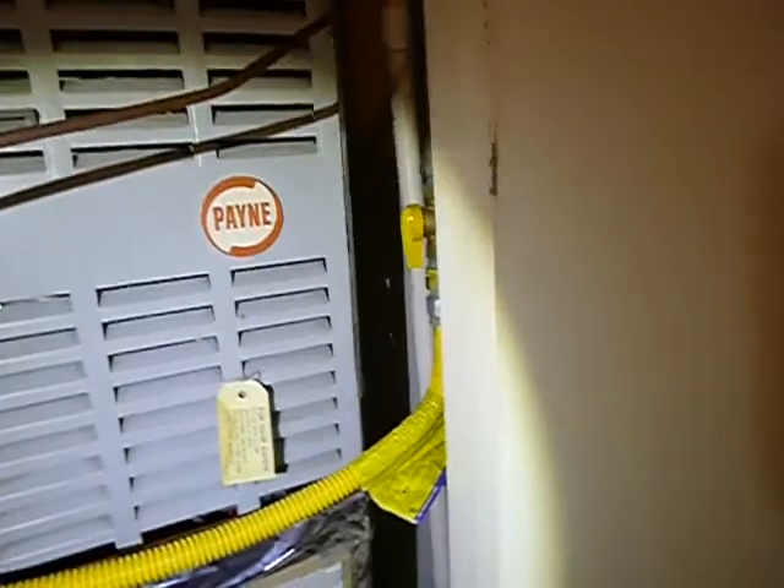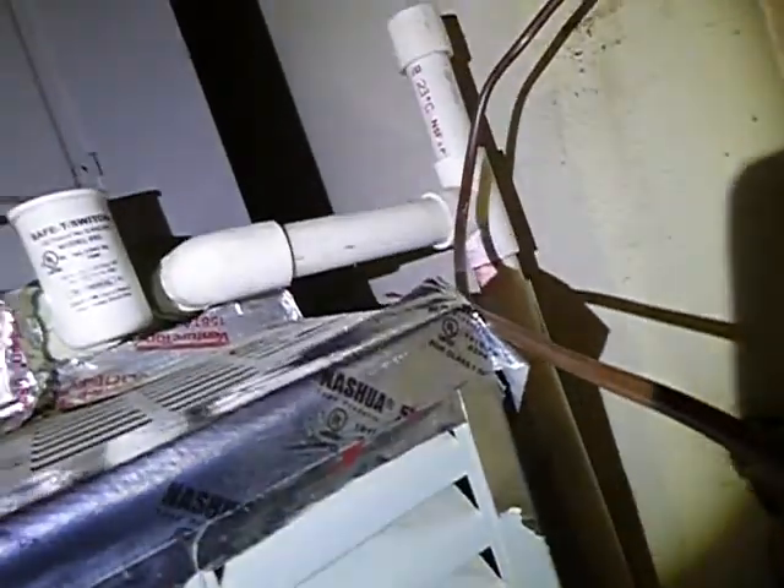We know that this furnace is older than six years old. It's obvious. But we're not taking it off today because it's all taped on, which is a deficiency in its own right. The flame's dancing around a little bit in there — a little too nervous for my comfort level. The gas line does not have a sediment trap.